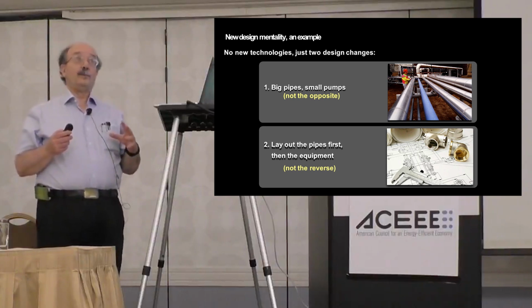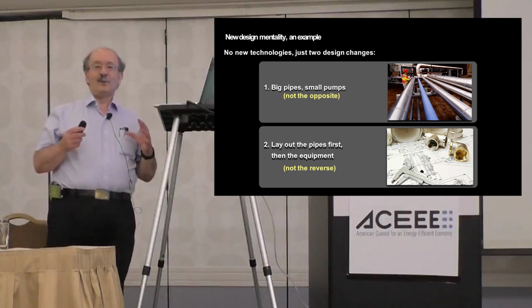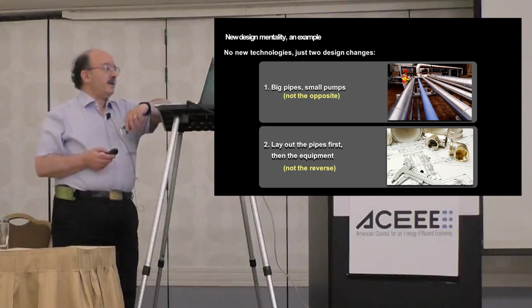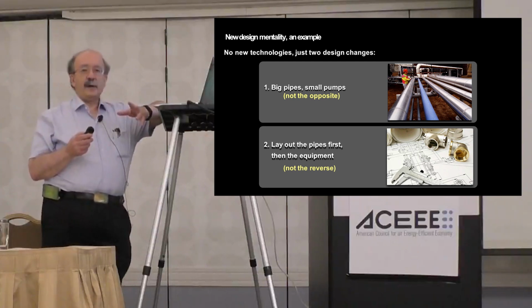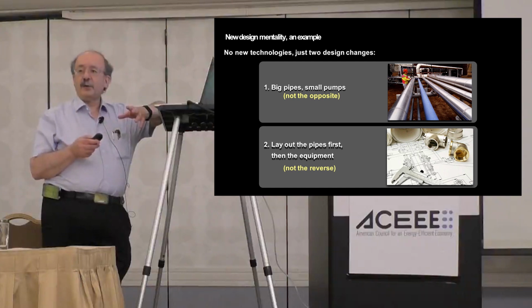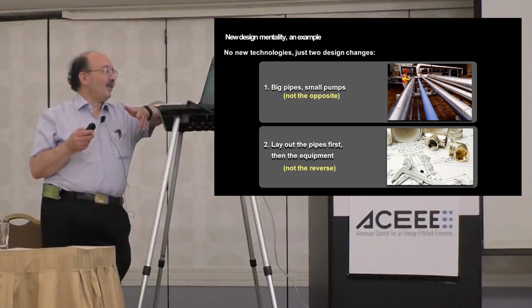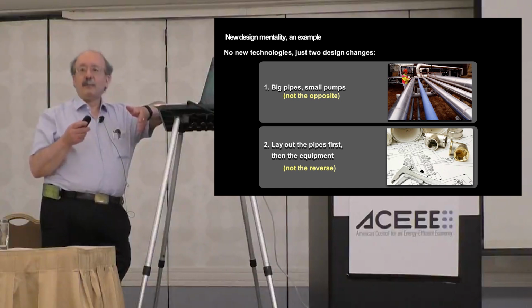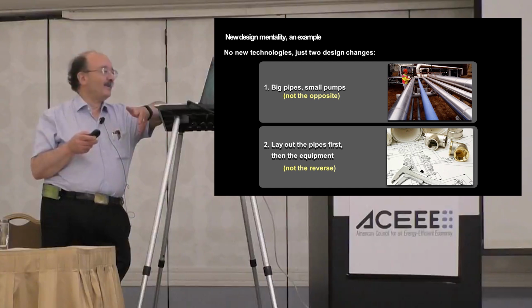Well, all but one of the engineering textbooks we've been able to find say to make the pipe just as fat as will repay its extra cost over the years from the same pumping energy. But that's wrong, because it leaves out the capital cost of the pumping equipment, which must also be big enough to overcome the friction. And therefore, the pump, motor, inverters, electricals size, and roughly their capital cost, will go down as nearly the 5th power of pipe diameter.